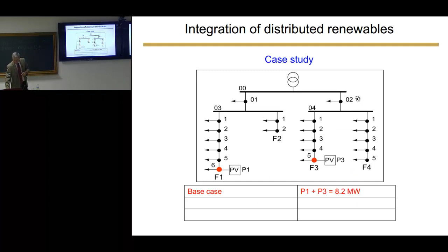I will skip this example. This example is intended to show you an initial situation, a radial configuration, where there is a limitation of PV penetration of 8.2 megawatts. If you add a DC link, an asynchronous link, and add 5 transformers with tap changers, you can increase almost 30% the capability to integrate photovoltaics just by adding hardware. And you don't have to upgrade the feeders, because if the feeders are urban, you need to dig the sidewalk, and you need to spend a lot of money in replacing or augmenting the capacity of the feeder system.